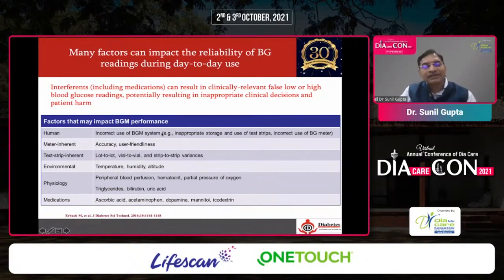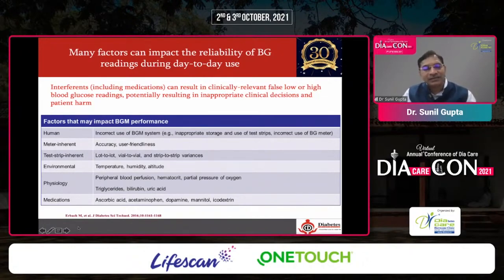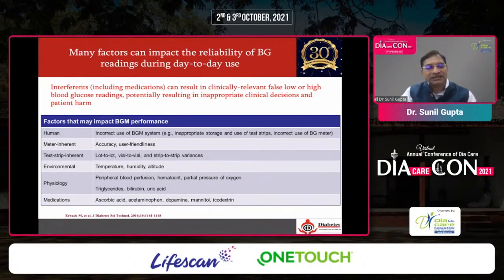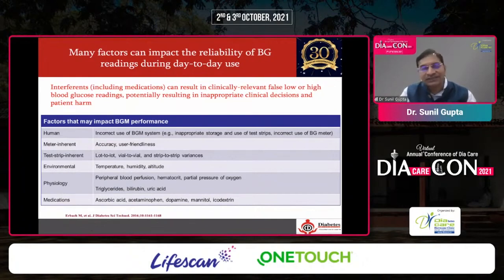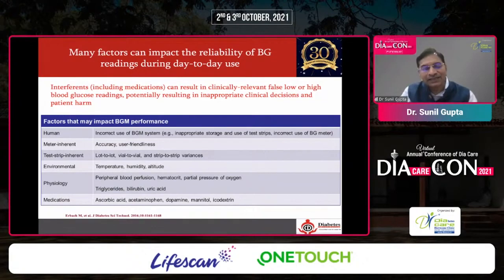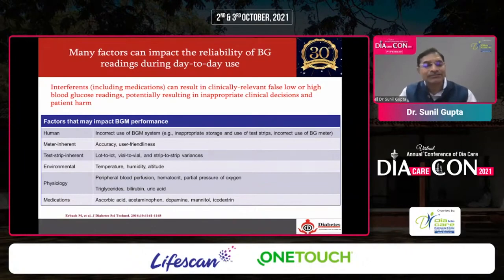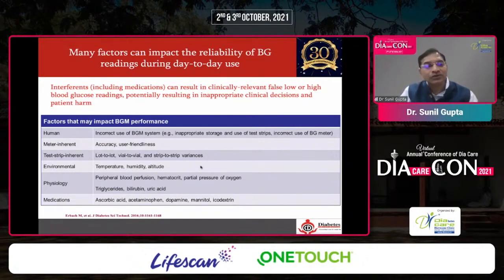One example from our own indoor facility: a nurse noticed that all readings were coming very low, whereas in the morning everything was fine. We investigated and found that an alcohol swab had accidentally fallen inside the strip bottle, spoiling all the strips and causing falsely low readings. This type of human error is not uncommon, and that is why we have to check these things carefully.